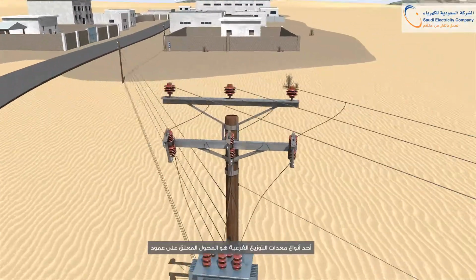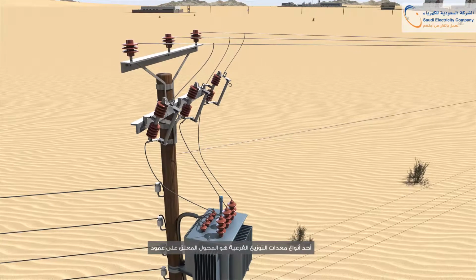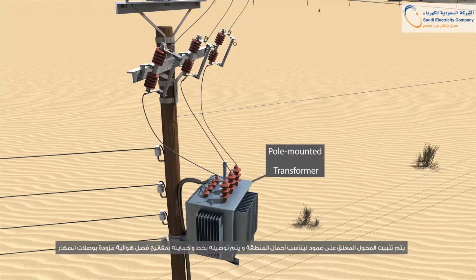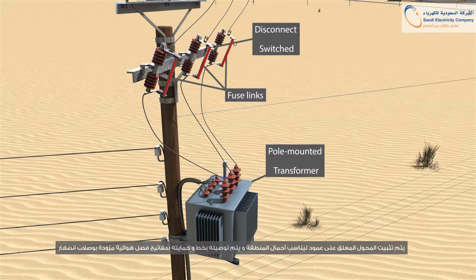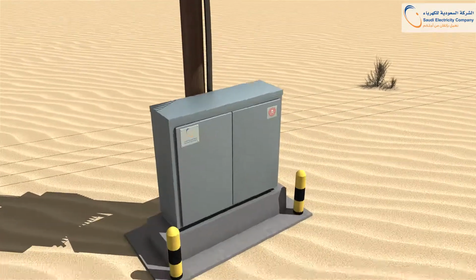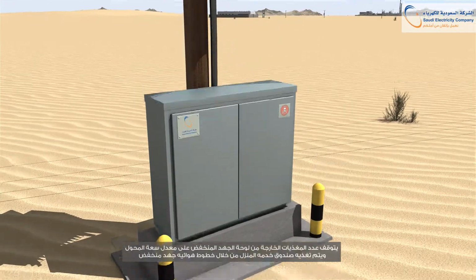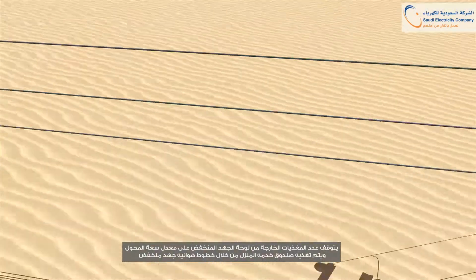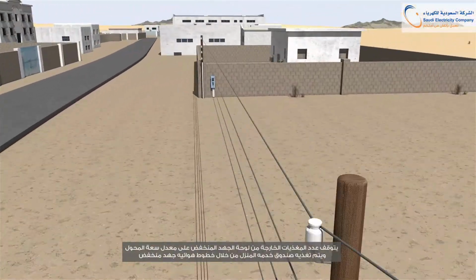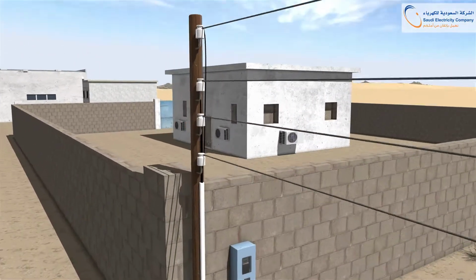One of the distribution substation types is a pole-mounted transformer. A pole-mounted transformer is fitted to suit loads of this area and connected to the line and protected by disconnect switches fitted with fuse links. The number of LV panel outgoing feeders depends on the transformer rating and feeds the house service box through low voltage overhead lines.